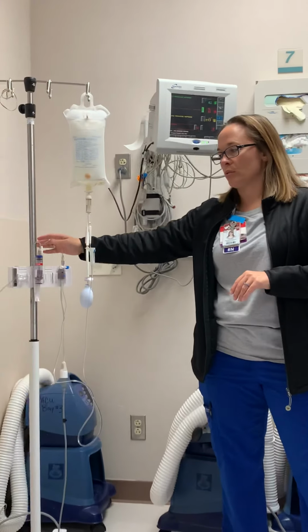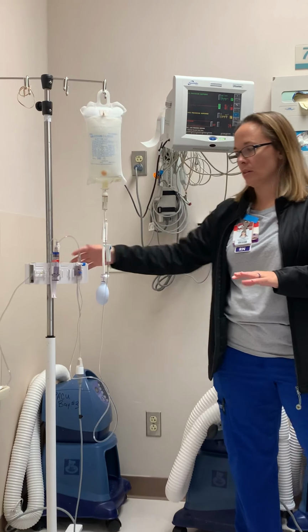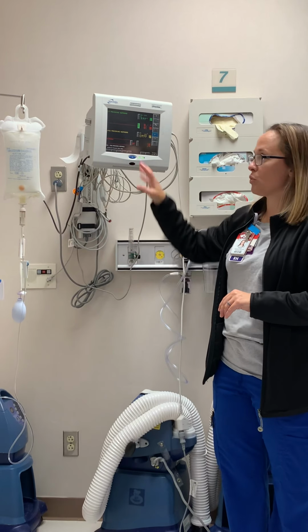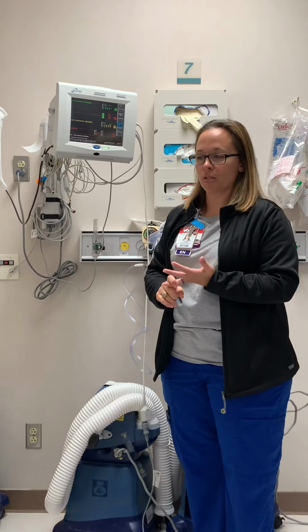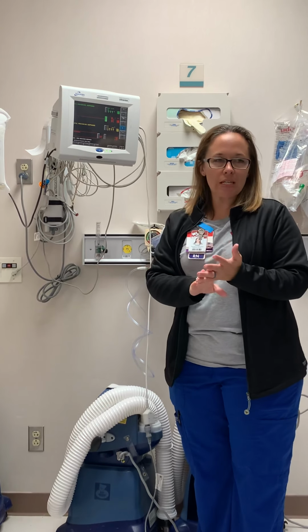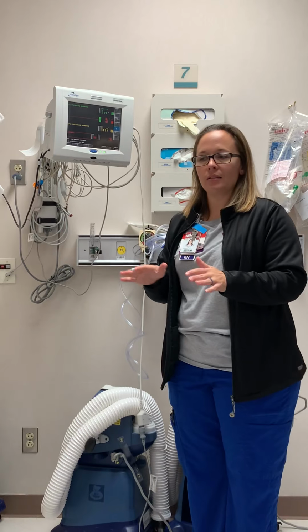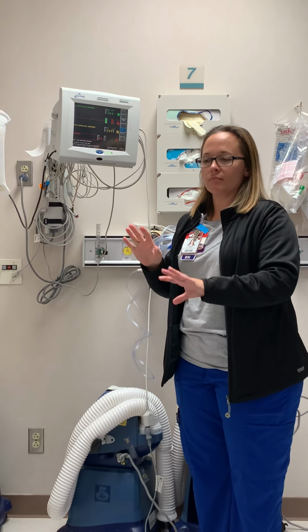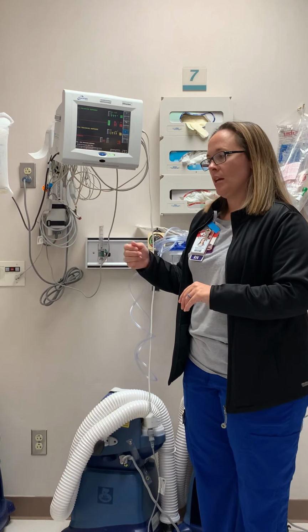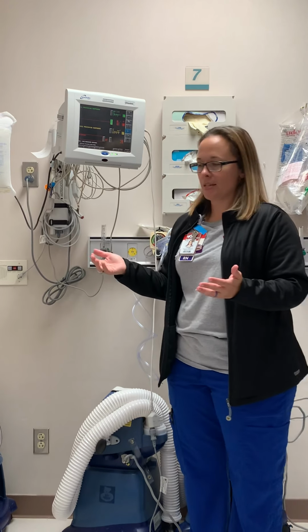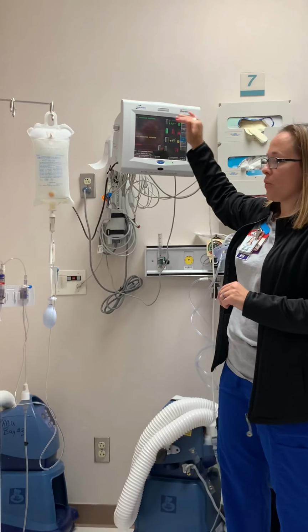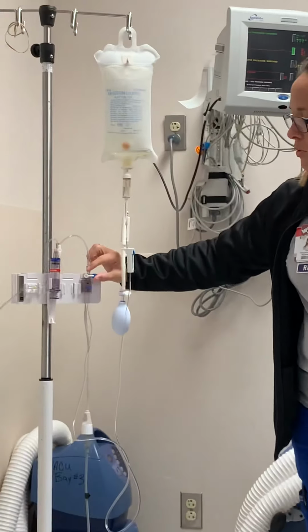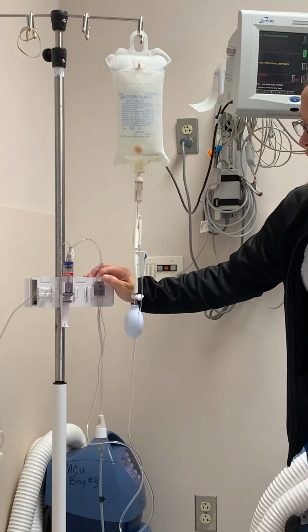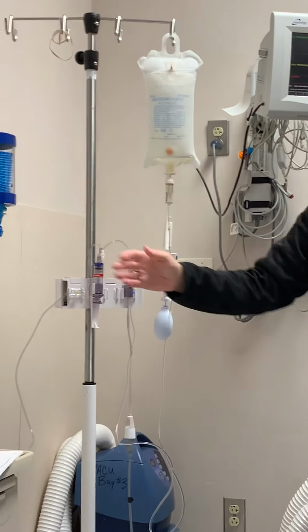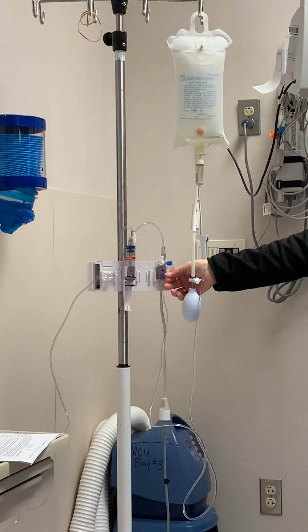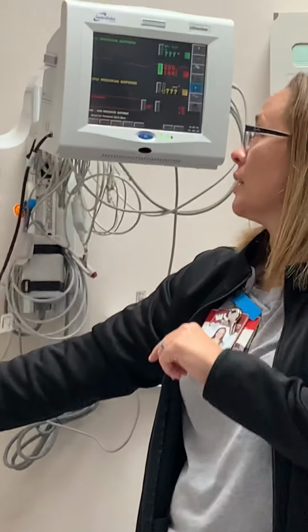But it's important though that this is at the level of the patient's heart. That can absolutely cause some issues where you won't see a correlation of the patient's blood pressure with the arterial pressure. That's an easy indicator. If you see an alteration or a difference in the blood pressure and the arterial pressure, that something needs to be done. You need to do a troubleshooting, and one way to do that is, of course, a square wave test. And the way to do that, it actually creates a square wave on the monitor. Whenever you want to do that, you flip this valve that's on the transducer up, and what it does is it blocks off the line to the patient. You pull your valve, and you'll see a square test.